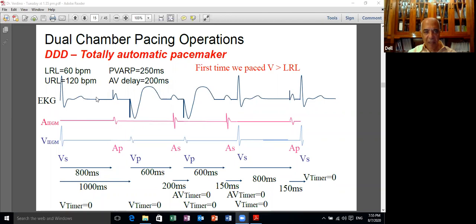So the VV interval is expected to be 1000 milliseconds as we mentioned before, but we have an AV delay of 200 milliseconds. So 1000 minus 200 milliseconds is 800 milliseconds. So after 800 milliseconds, nothing is felt by the pacemaker, atrial or ventricular leads. So there is a pacing of the atrium. After pacing the atrium, the AV clock starts to work, counts 200 milliseconds, which is the AV delay. If nothing is felt, we throw a spike and we pace the ventricle. After we pace the ventricle, the ventricular timer goes down to 0.